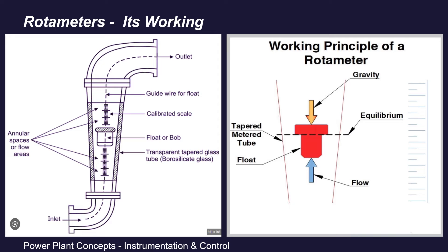As we can see in the diagram, the red one is the float. The fluid flow from the bottom is exerting pressure on this float and the float is rising up. As it rises up, the annular space between the float and the tube walls increases — since this tube is tapered in shape. So more fluid can flow through. The larger the amount of fluid flow, the higher the float is raised and thus more will be the annular area to allow passage of flow.